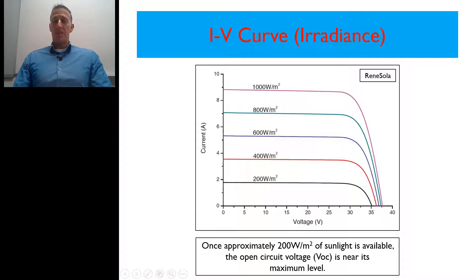That's when we're calculating the maximum voltage a solar PV system will put out. We're talking about that cold temperature right when the sun pops up or basically starts illuminating the sky and it starts to get brighter and brighter in the morning. It's about that time before the system is actually even turned on and starts generating current. That's when we're going to have that maximum voltage.